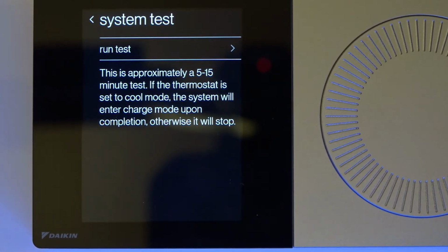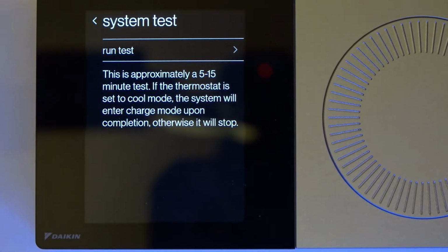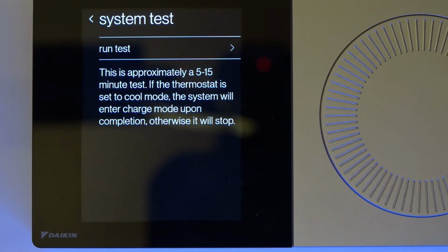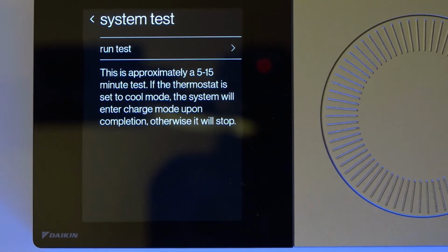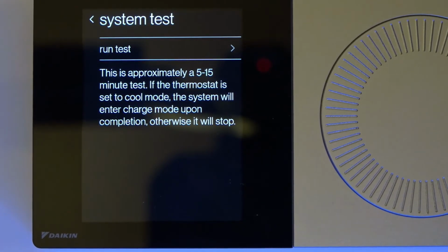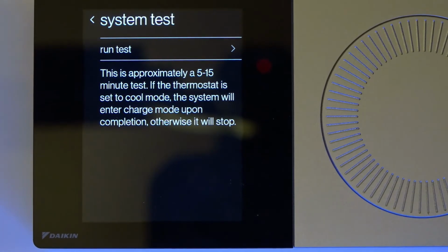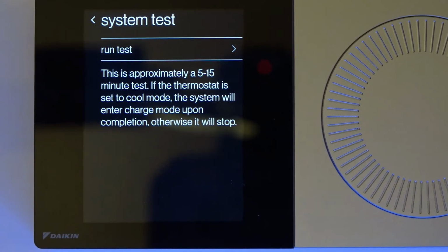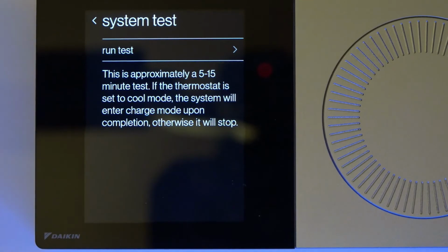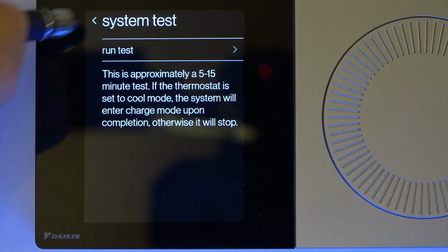When you hit this run test, just let it run. There's nothing that you can do to stop it. That's why I'm not going to hit the button right now, because I'd have to pull the thermostat or kill the power to be able to stop this test. It'd have to run for 20 minutes. But it's going to check itself out. It's going to turn the fans on, the blowers, the compressor. It's going to run everything, then look at all the thermistors and pressure transducers to make sure everything's talking. And after about 15-20 minutes, the little spinning dial over here will stop.